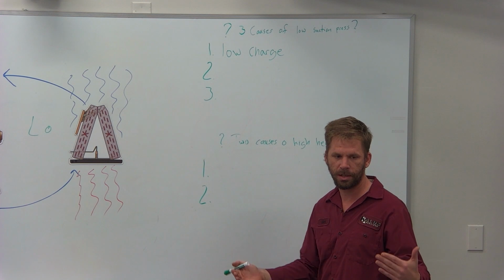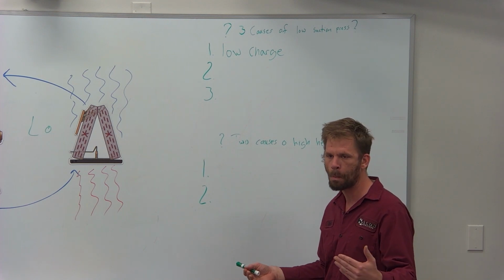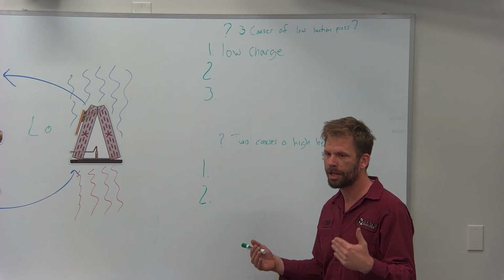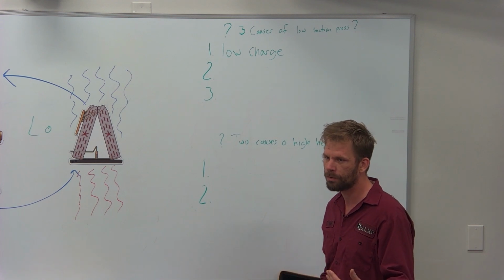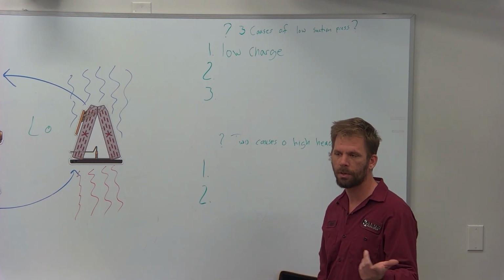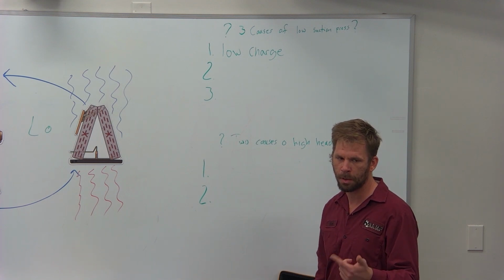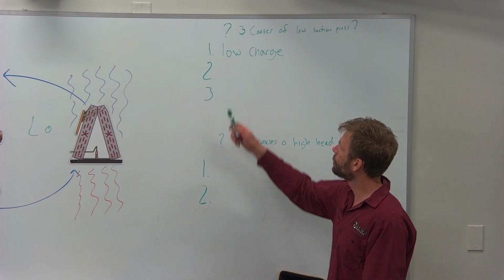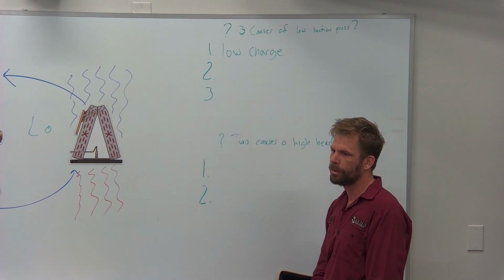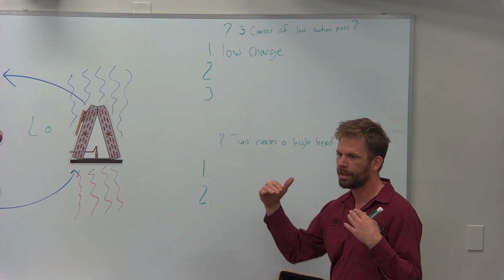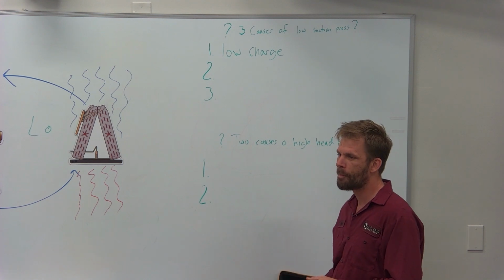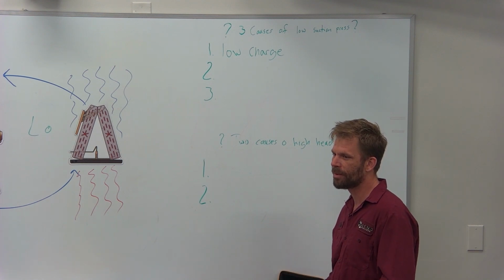Understand, when you guys are training other people, when it's your turn, or when they're training you, there's a language to learn in the trade. If you said low refrigerant, he would have figured out what you meant immediately. Same thing. Low charge is the low level. If somebody has added refrigerant and they set it at a low charge. Yeah, because in my head, I went to the controls in the outside unit that will have an actual electrical short. Electrical, no. Low charge. So, is exactly right.